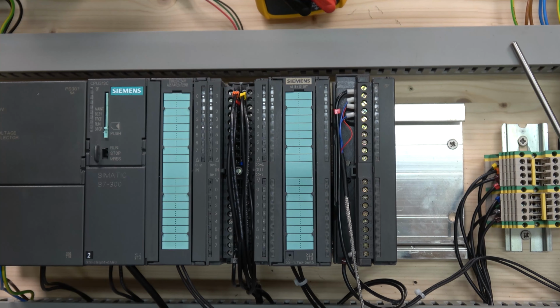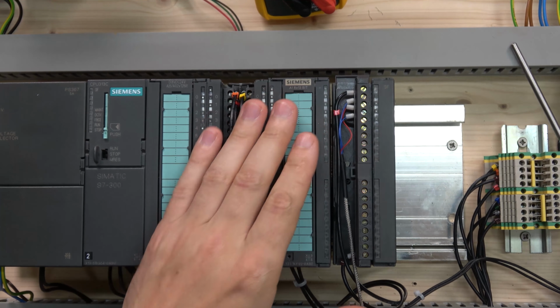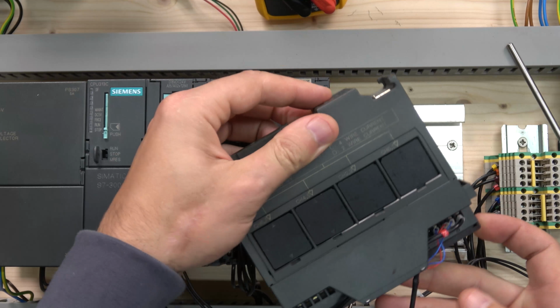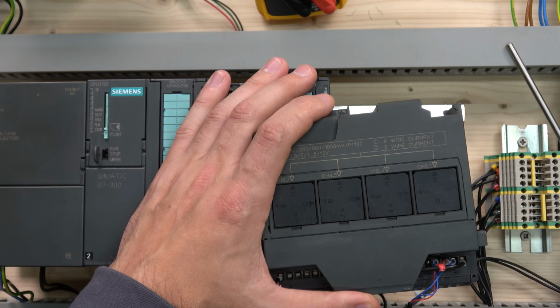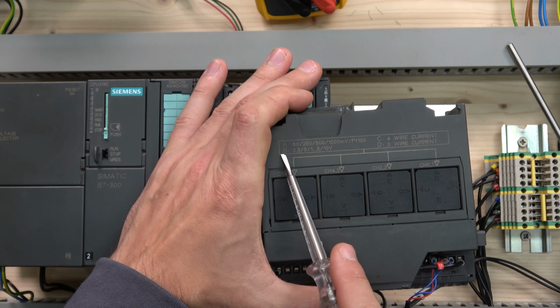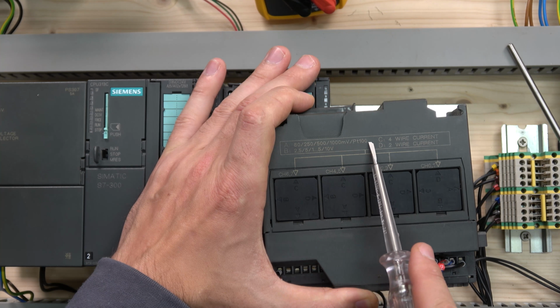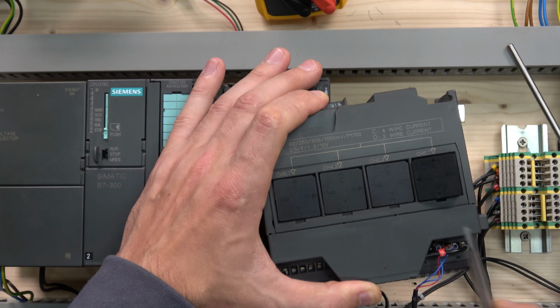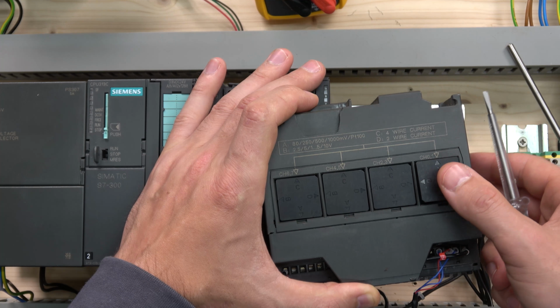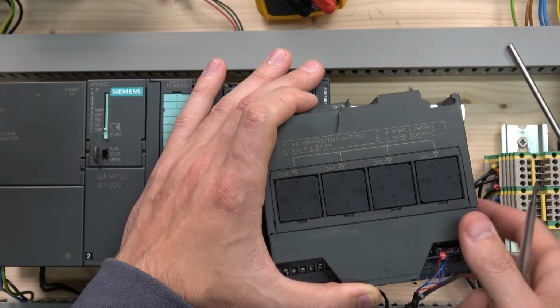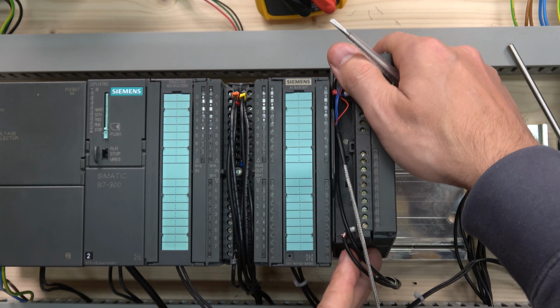So for the 7KF, you unplug the card. As usual, we need to make sure we are selecting what we are trying to do in here. Remember, this comes with diagnostics as well, which is awesome. So we're going to show you at the end of the video what happens when your temperature probe disappears. So what we need is this one in here, which is the A, which pretty much tells you it's PT100 and all other resistors. So let's unplug that and change that to A. So that's the one we're going to be using. And yes, in the next video, we're going to be playing with the TC temperature probes. We're going to use the same channel.